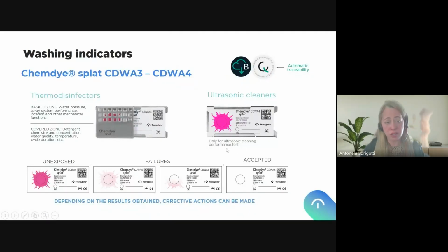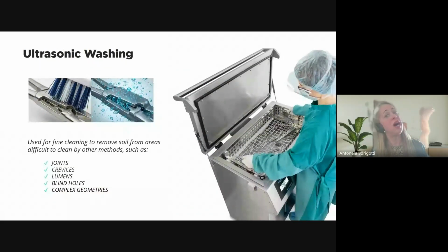So depending on the results, we can design a corrective action. This will be the initial, as you can see here also. The accepted result is a total removal of the test soil. And depending on the residues remaining on the indicators, I can make a decision about chemical or physical problems and take corrective actions. We have to cover too many indicators, so I will go quickly with this one, but in case you have questions, we can review that later. We also have ultrasonic cleaning, and this machine has a little difference.